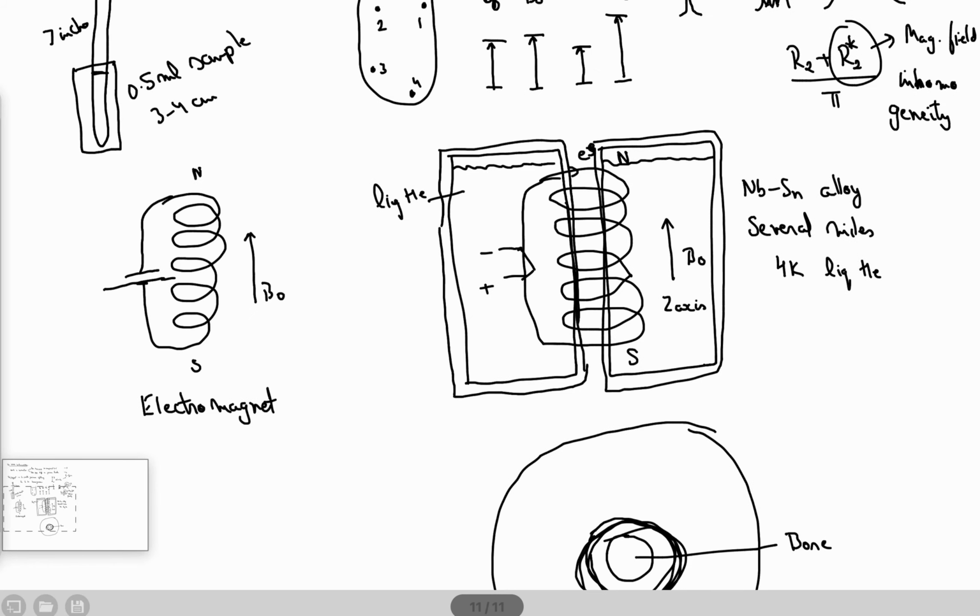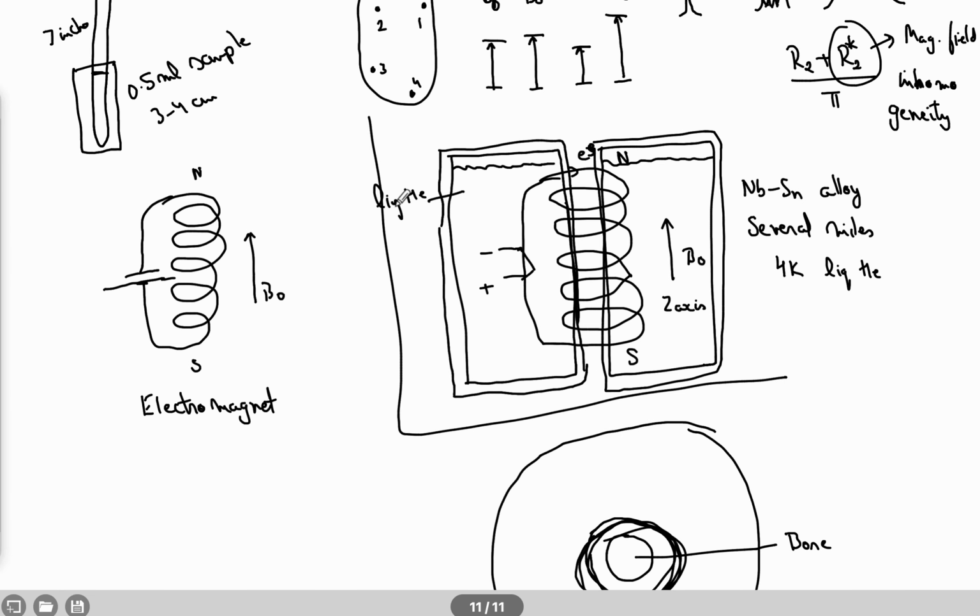And then further, this whole thing is immersed into liquid nitrogen. Okay, so liquid nitrogen further stops liquid helium, or decreases the evaporation rate of liquid helium. Because liquid nitrogen comes cheaper, it is better to fill liquid nitrogen.